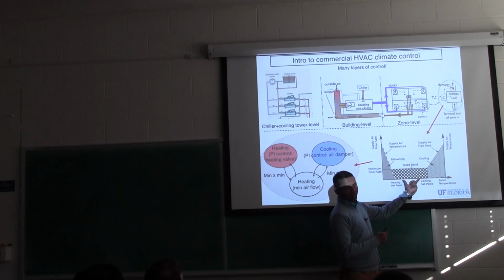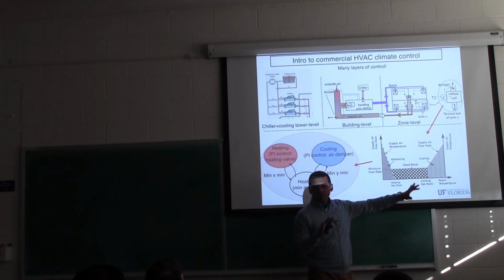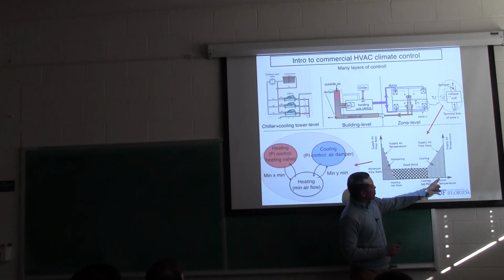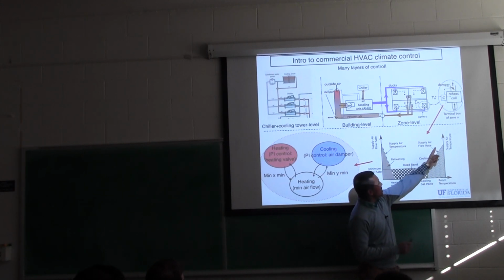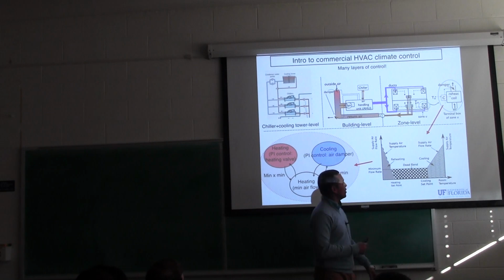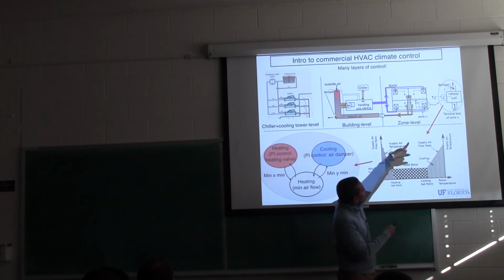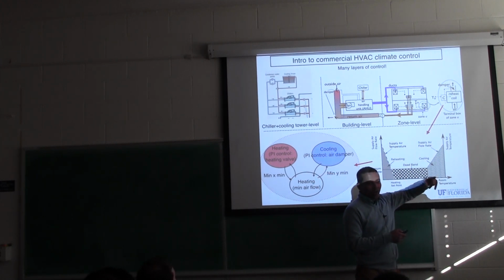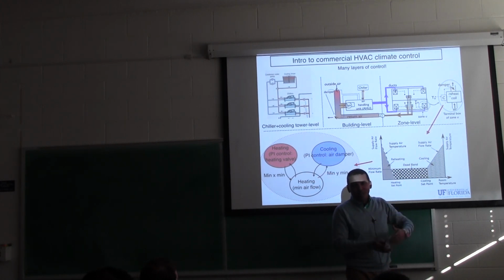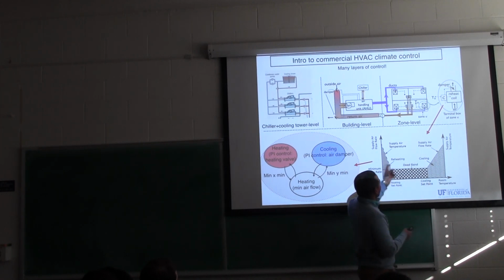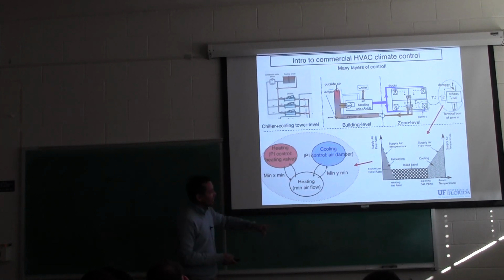This is called a dead band. If the temperature is in this range, then you just supply some nominal airflow, you're fine. If the room becomes too hot, then you increase the supply airflow rate to make it colder. If the room temperature becomes too cold and you want to heat it, you keep the airflow the same, but there's a reheat coil. You turn on that coil and ramp up the heating so that you actually get more heating. And this picture also is not the full picture.